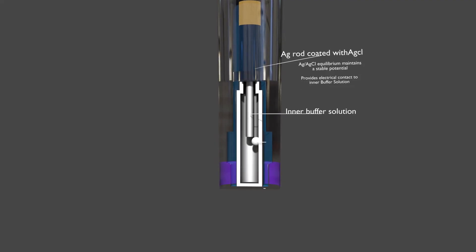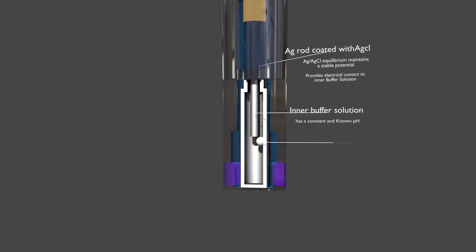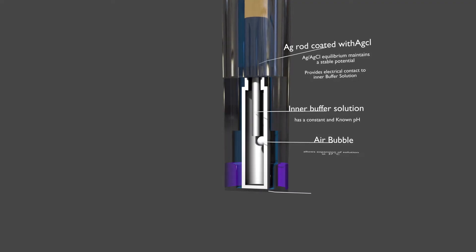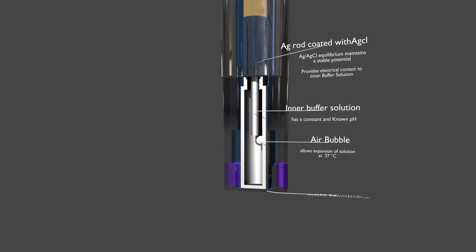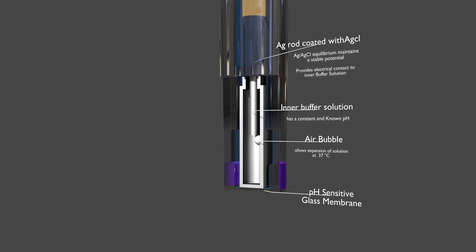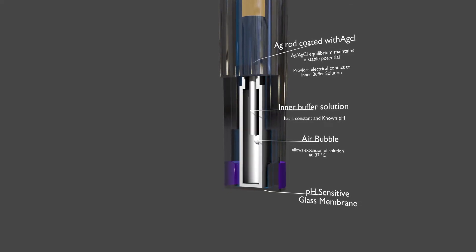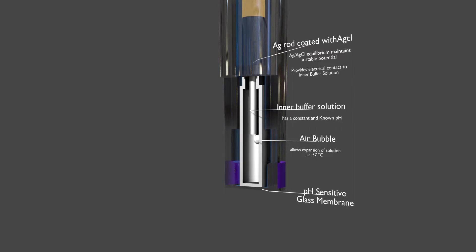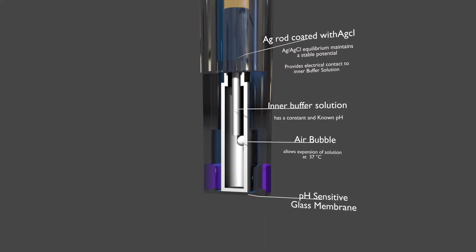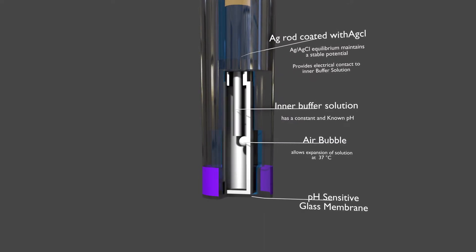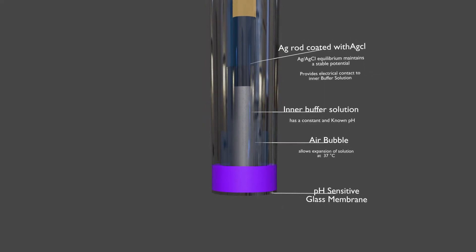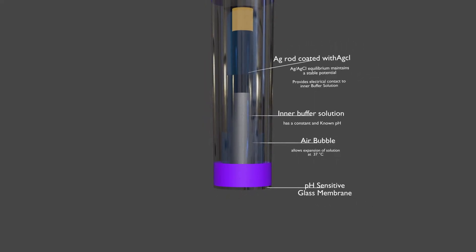Charge is displaced across the membrane resulting in the flow of current across the glass. One side of the glass is exposed to a buffer of known pH, reference electrode. The other side is exposed to blood, test solution. The glass membrane is then a partition with differing hydrogen ions on either side, establishing a potential difference via the concentration gradient. The pH remains constant despite the change in hydrogen ions due to the action of the inner buffer solution.